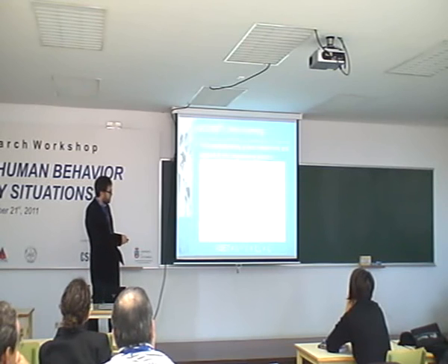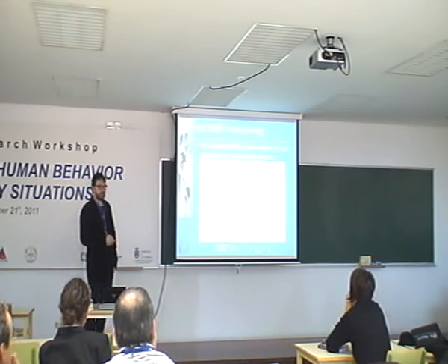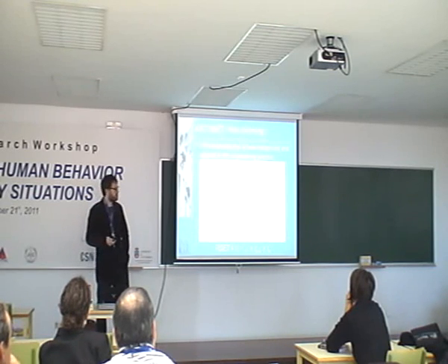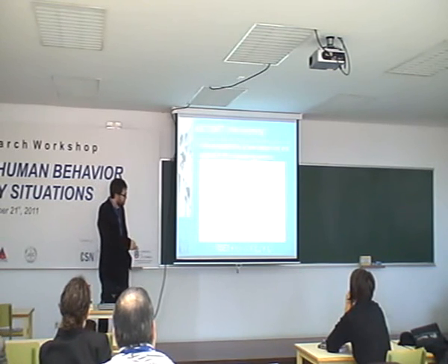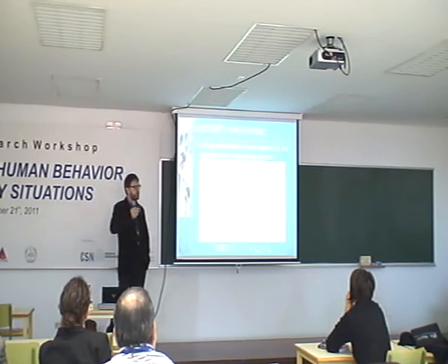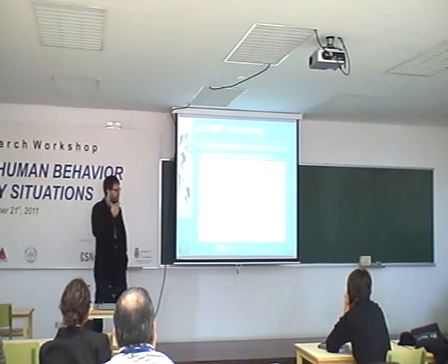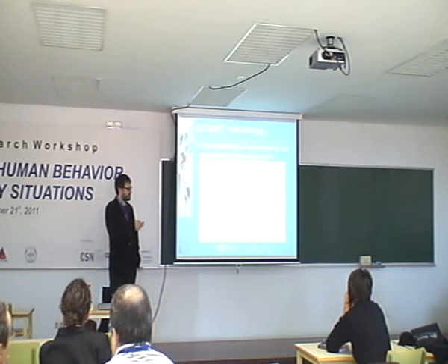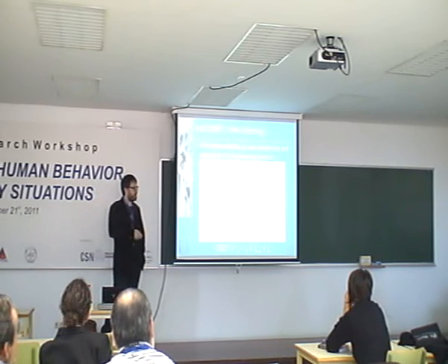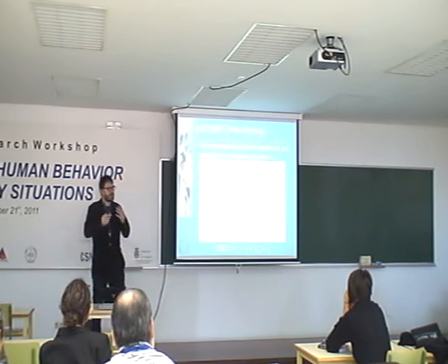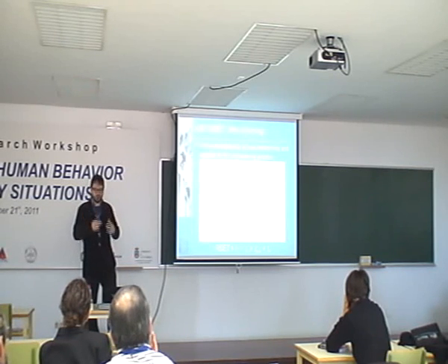So oftentimes we account for the pre-evacuation time and the overall evacuation time using complex simulation tools or engineering calculations, but we account for the detection time using manufacturer's guidance. So if a certain temperature is reached or a smoke density is reached, then the alarm will sound. And then for notification time, the automatic time is assumed given that a fire has been detected, rather than any procedural actions that are required within that structure.